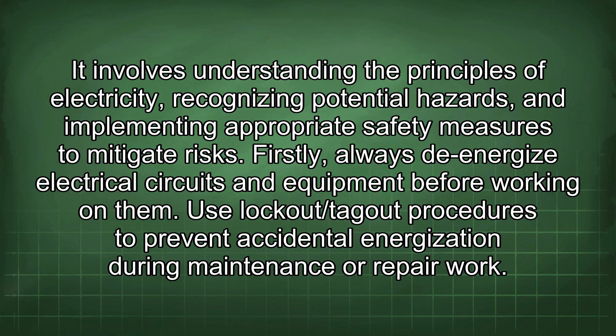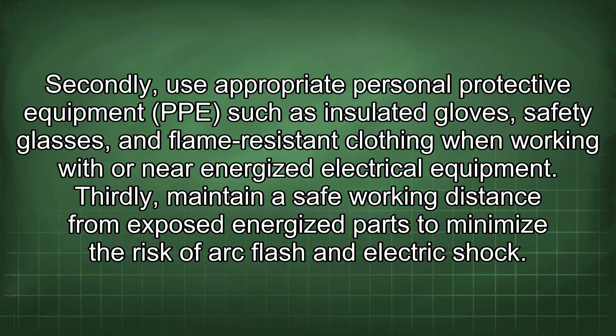Secondly, use appropriate personal protective equipment (PPE) such as insulated gloves, safety glasses, and flame-resistant clothing when working with or near energized electrical equipment. Thirdly, maintain a safe working distance from exposed energized parts to minimize the risk of arc flash and electric shock. Refer to safety standards such as NFPA 70E for guidance on safe work practices and approach distances. Fourthly, regularly inspect electrical tools and equipment for damage or defects. Remove any damaged tools from service and repair or replace them as needed. Fifthly, use ground fault circuit interrupters (GFCIs) in wet or damp locations to protect against electric shock. GFCIs detect ground faults and quickly de-energize the circuit to prevent injury.